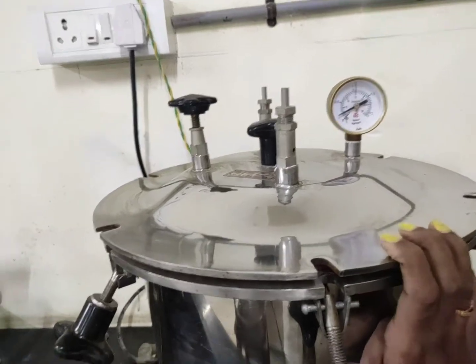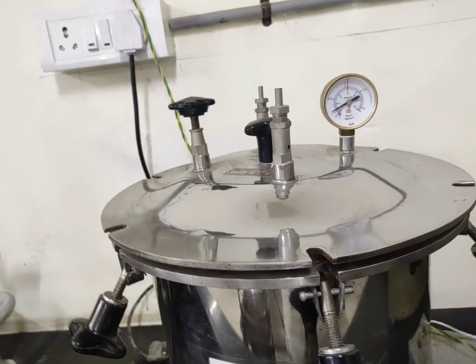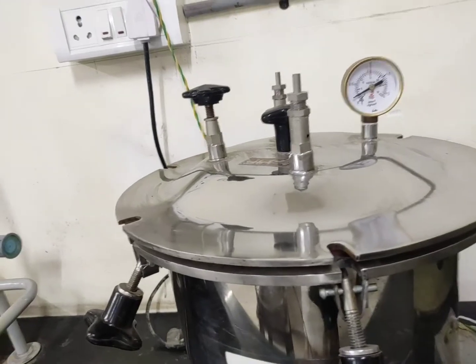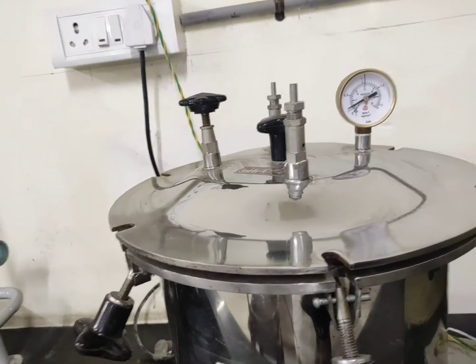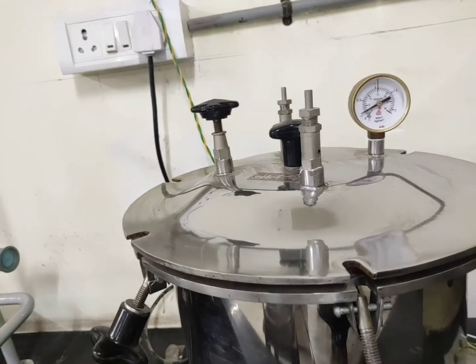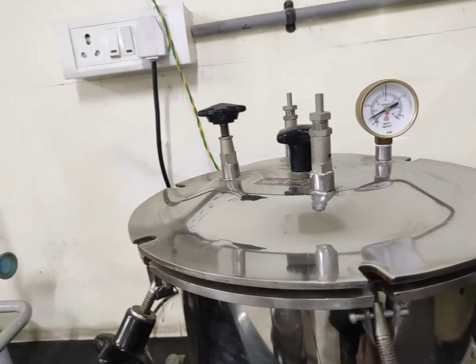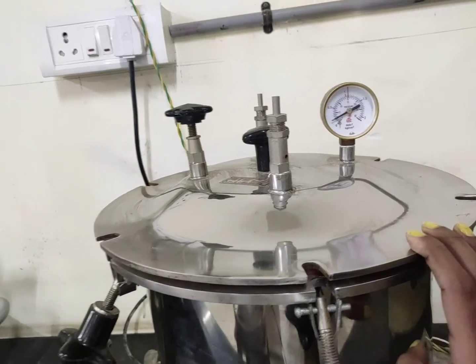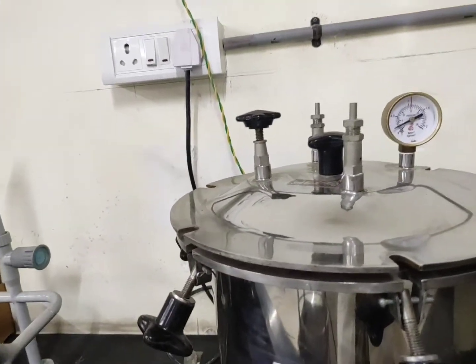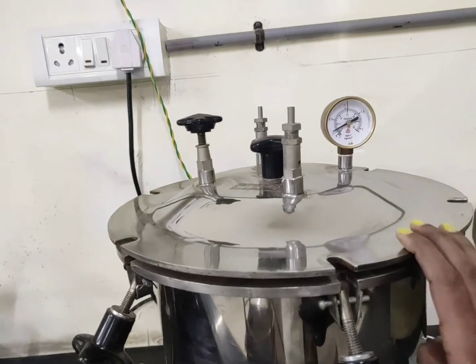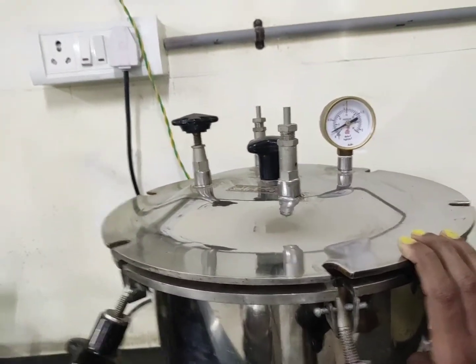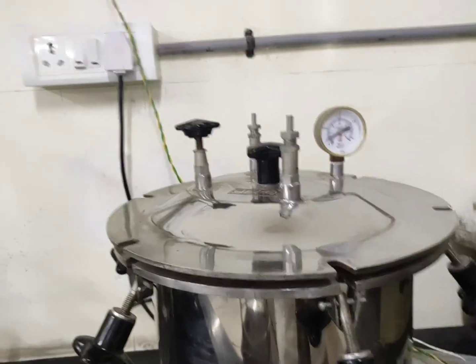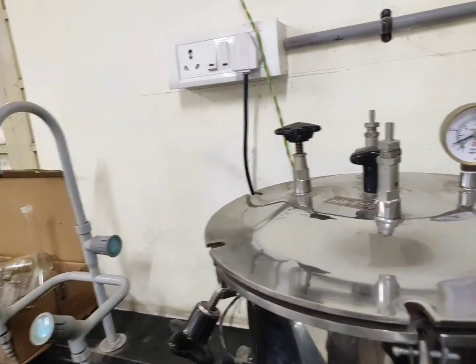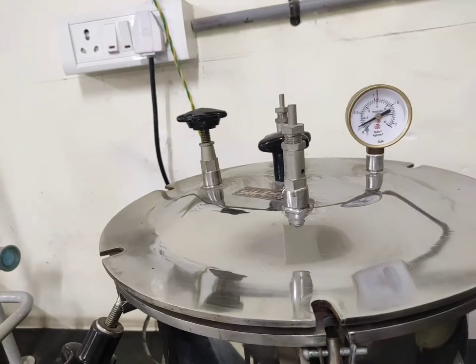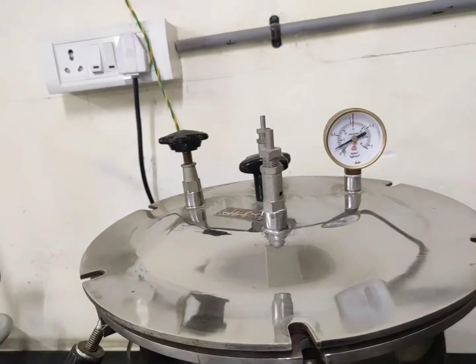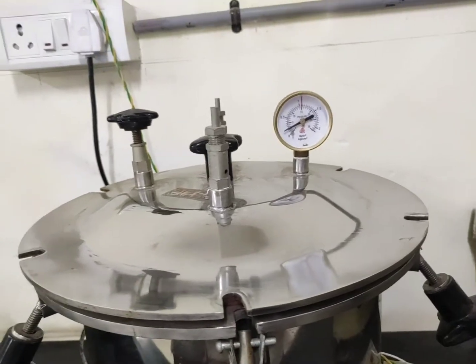Once you put the sample inside, because of the pressure the cell will rupture, and you can take that ruptured cell in order to get the extract out of the cells. The next thing you have to take care of is, since the temperature increases very high inside the instrument, you are not supposed to put any plastic materials, and even your glass measuring cylinders, which are very accurate. Otherwise, because of the heat, those will expand. Your other glasswares which you want to autoclave or sterilize, those you can keep.